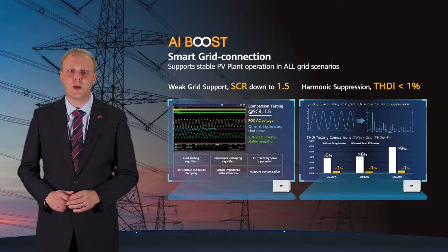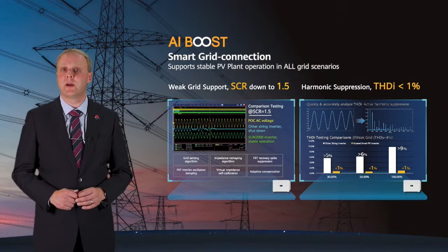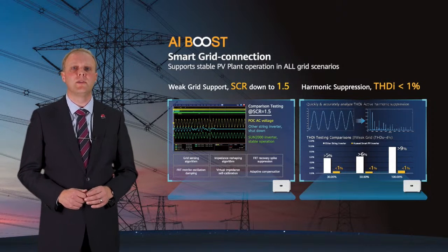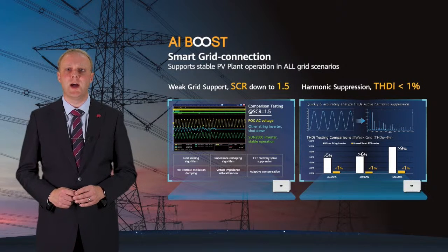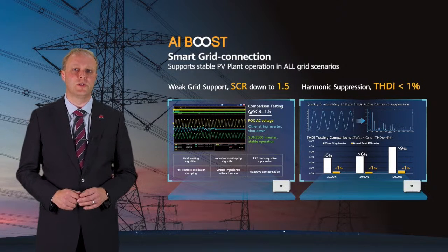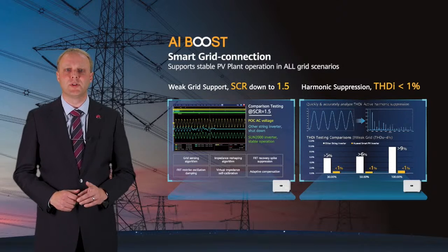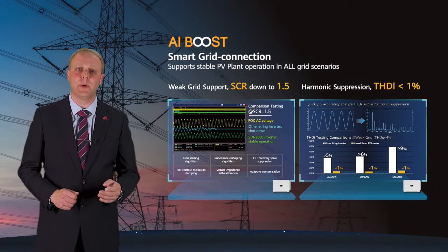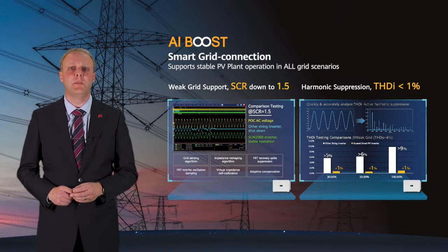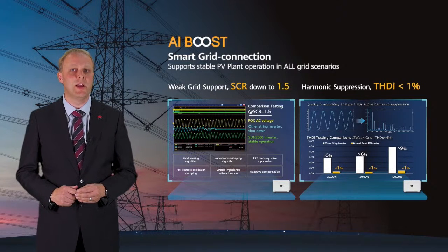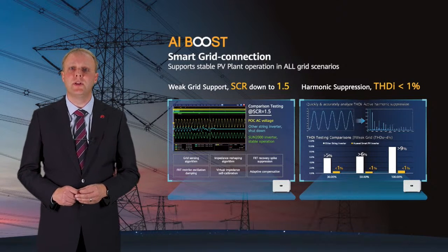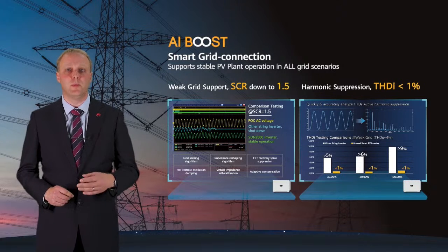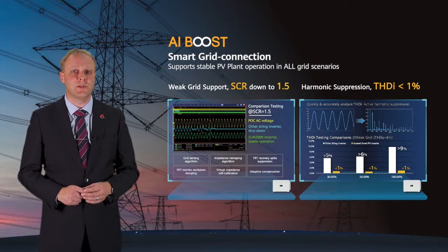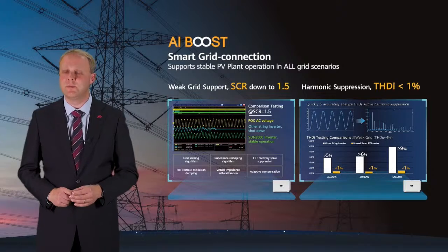In terms of power quality, in a real power grid with background harmonics, Huawei inverters can ensure that the THDI, the current harmonic distortion, is less than 1%. In comparison, other string inverters can barely achieve the claimed THDI of less than 3% even in laboratory conditions. In real power grids, the harmonics of such inverters can surge to more than 9%.